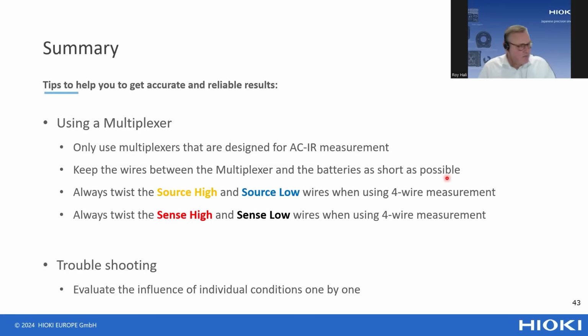If we look at multiplexers, only use multiplexers that are suited for ACIR measurement. Make sure that you check that before you start using multiplexers in the production line. And basically then the same things are applicable as for the regular wiring. Make sure that you twist the source and twist the sense wires and keep wires between the multiplexer and the battery as short as possible. For troubleshooting, the message is always do it one by one. So change one of the possible causes and do a measurement. And step by step find out what the cause of your problem is.